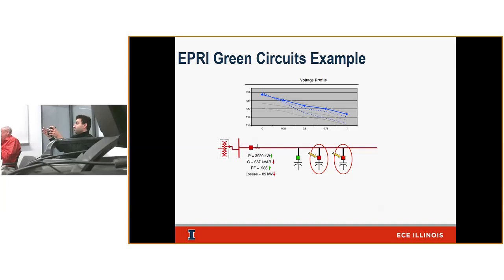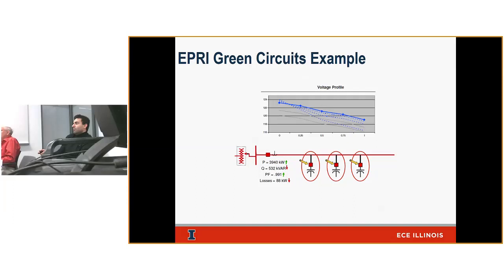To get to a place where you can reduce the voltage, you will have to compromise and temporarily see more energy. Here's my second cap bank closing: same effect — power factor improved from 0.97 to 0.98, losses reduced, VAR flow got better, voltage profile went up. The first dotted line was my original case; the second dotted line is after closing the cap bank showing further improvement. Then I close my third cap bank: power factor improved again, losses were reduced, and overall VAR flow reduced for a much better voltage profile.